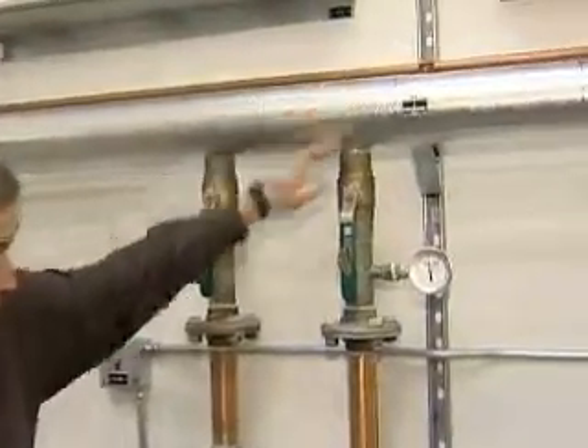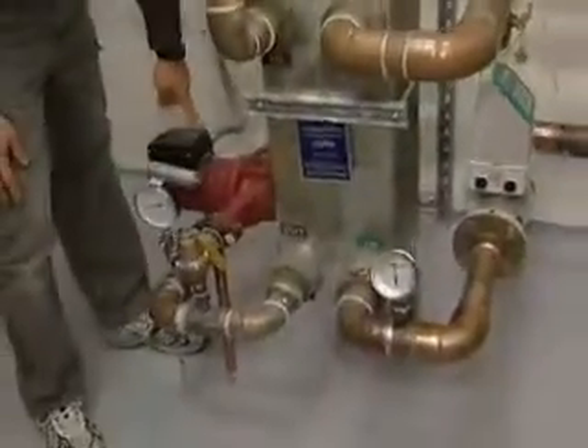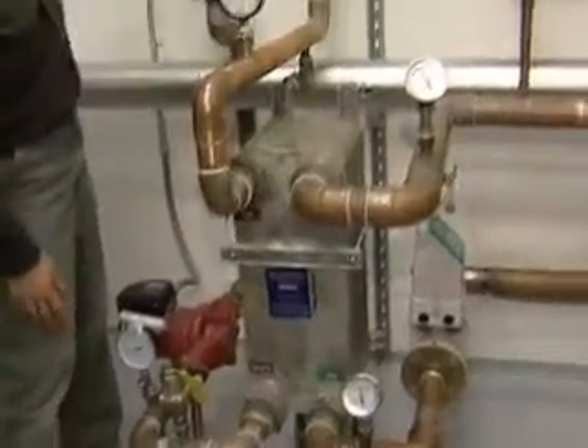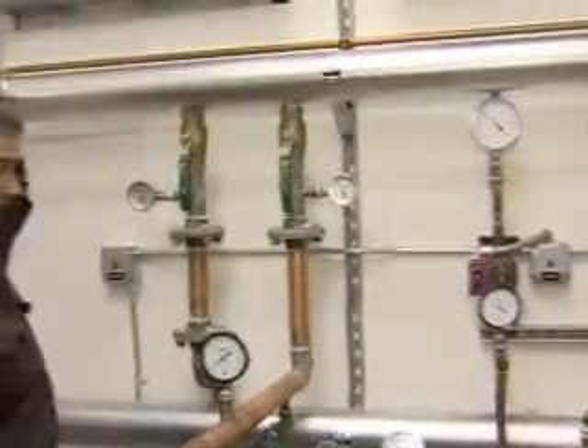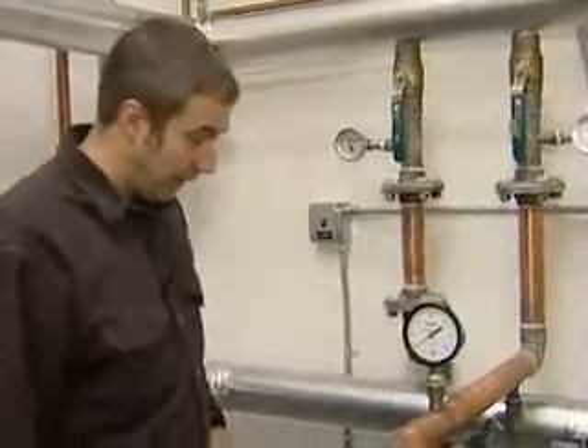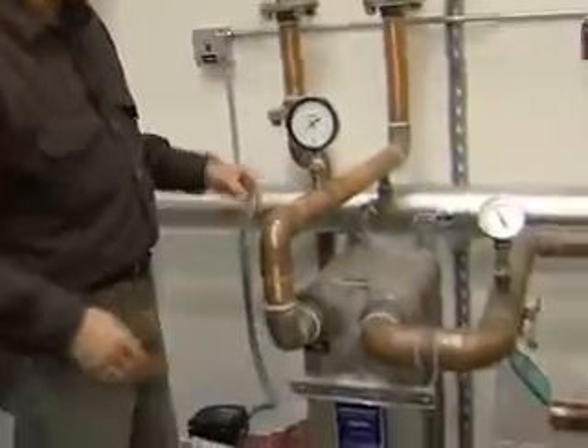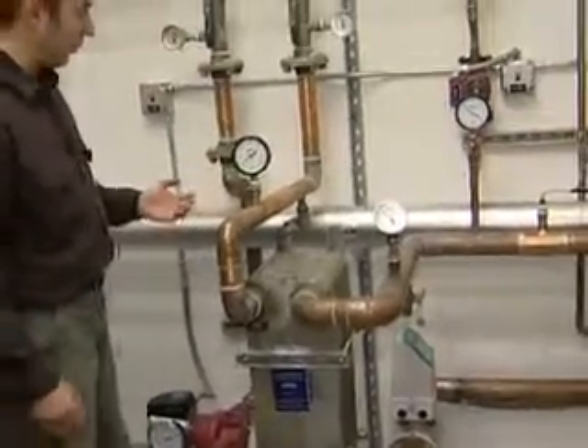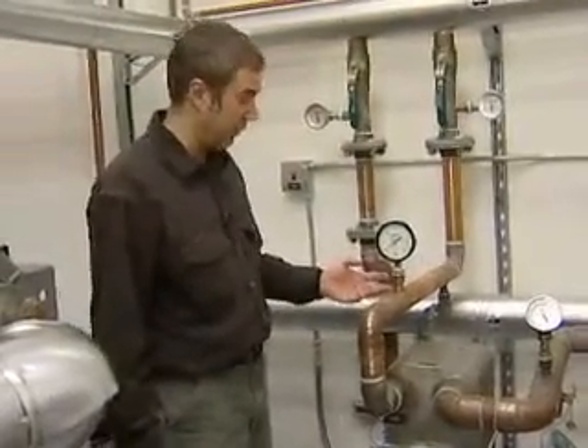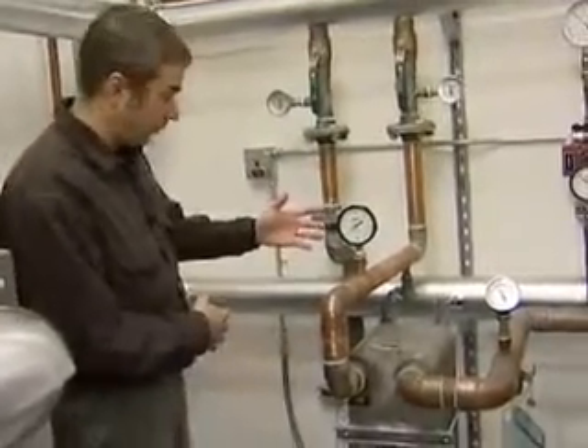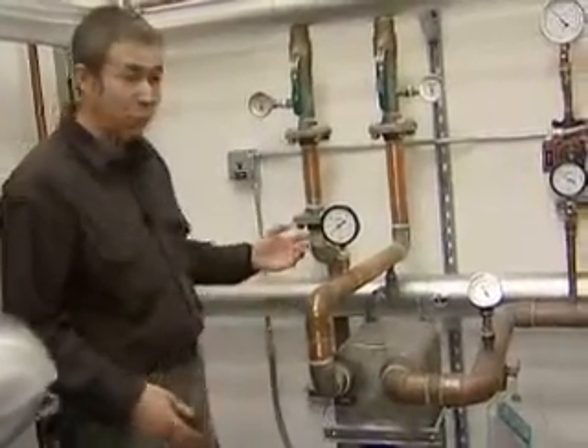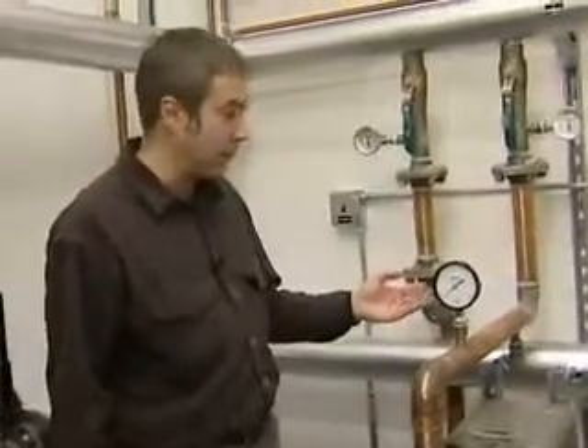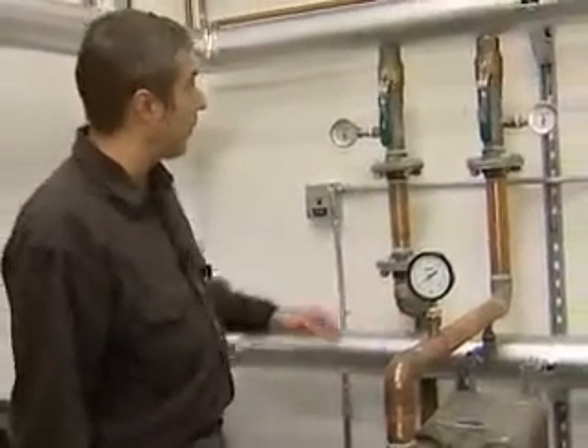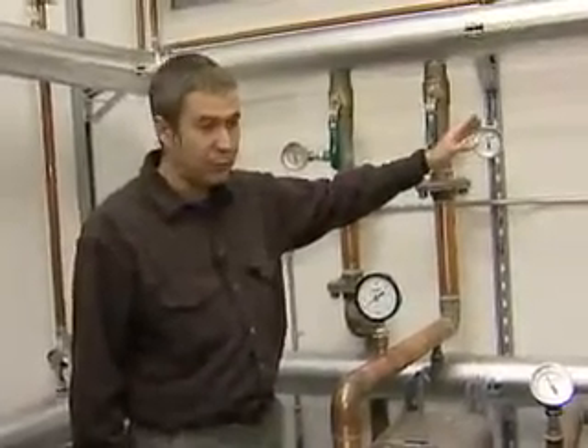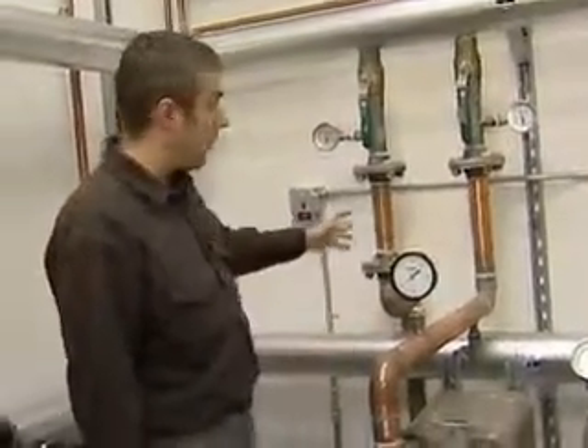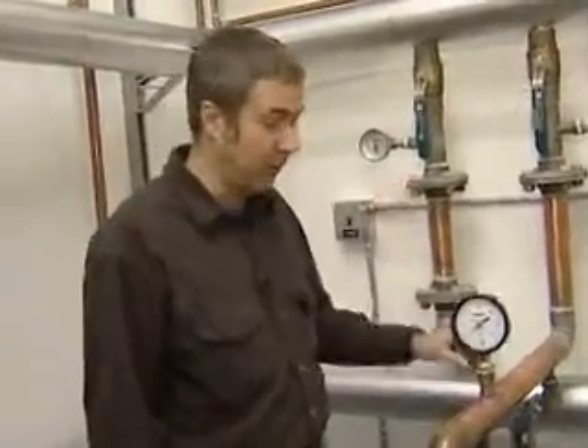So we come off the hot coolant line, run through the heat exchanger, here's the pump that does the circulation, come back up and return into the engine coolant line, then it can go on back to the radiators. And this side of the heat exchanger will operate under normal conditions at the same pressure and temperatures as the engine coolant piping because it's tied directly to it. The system is shut off right now, so our pressure is down, but under normal conditions you would see a pressure of 3 to 5 psi, and you should see temperatures coming into the heat exchanger of maybe 180 to 200 degrees, and then coming out will vary depending on the amount of load that's on the heat exchanger.